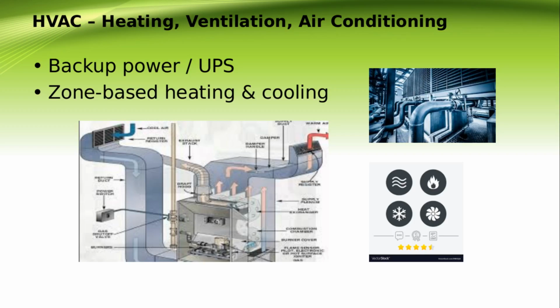When doing facilities planning, you need to take into consideration the cooling requirements of computer data centers and server rooms. The amount of heat generated by some equipment is extreme and highly variable. Depending on the size of the space, age, and types of equipment the room contains, energy consumption typically ranges from 20 to 100 watts per square foot.